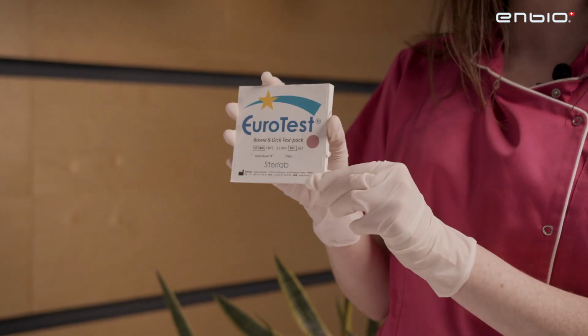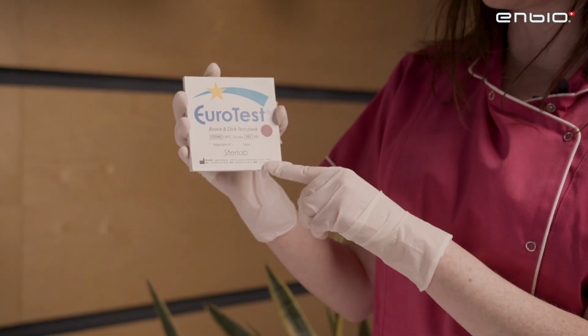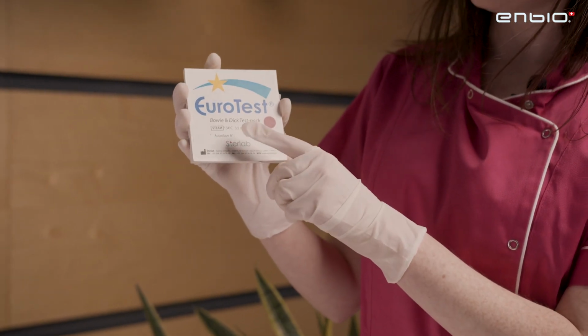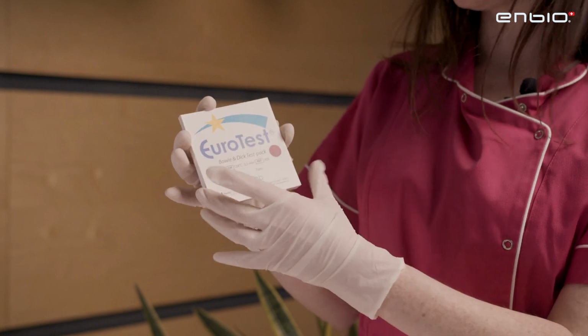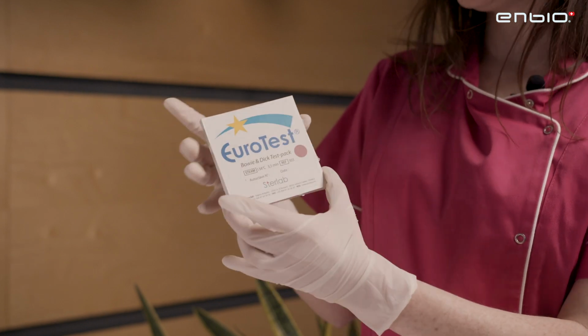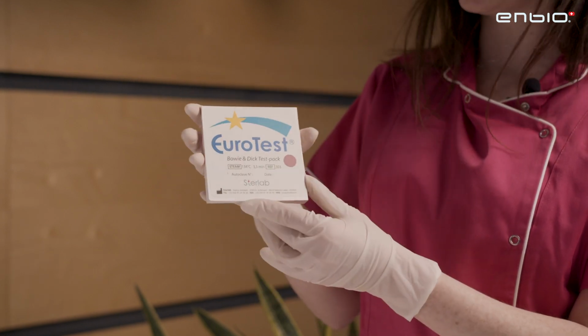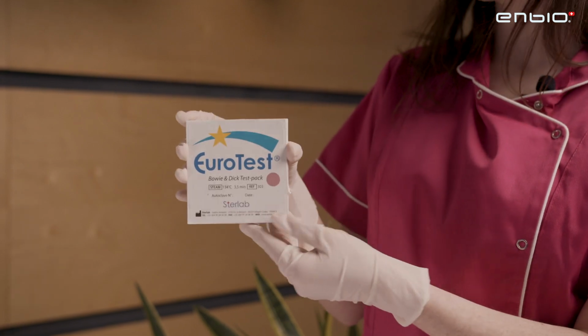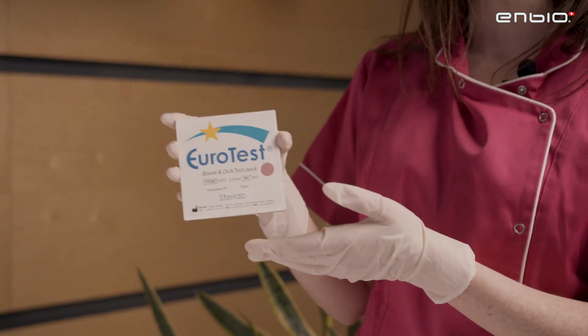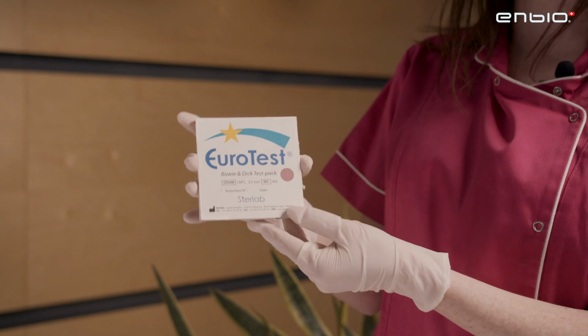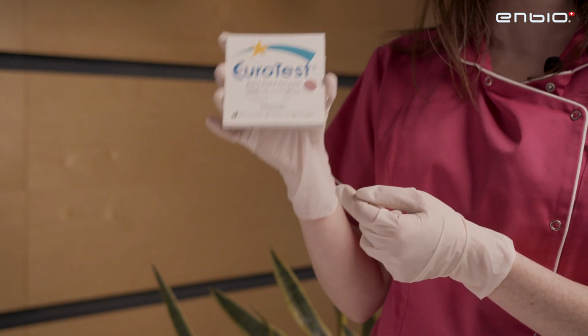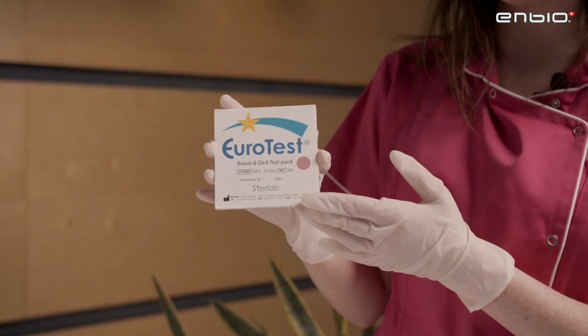And the test should be inside the autoclave for at least 3.5 minutes. And when we perform this test, it's important to not have other tools inside the autoclave. So we should only have the Bowie and Dick test inside the autoclave.